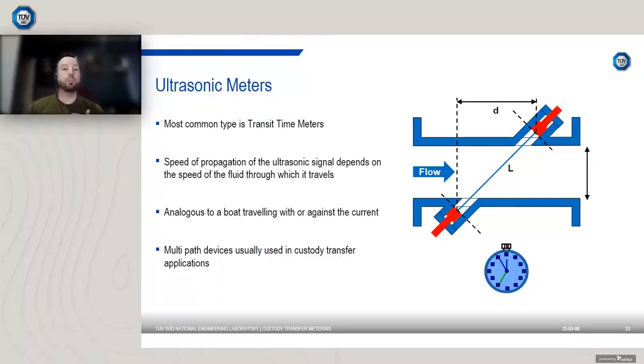Now why is it important to use a multi-path device? Well, if you took a cross section through your pipe and looked at the velocity profile of your flow, it's not going to be uniform. So in order to determine an accurate average velocity profile, you usually need to use more than one path. So the more paths you use, the more accurate the meter tends to be. A good thing about multi-path devices as well is they have built-in redundancy. So if a pair of transducers fails, you've still got other pairs that can perform the measurement.